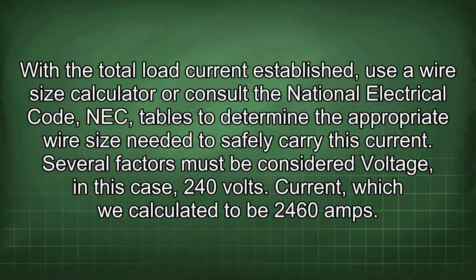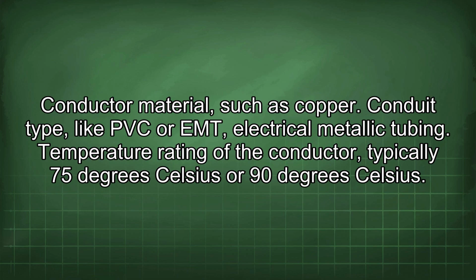Current, which we calculated to be 2460 amps. Conductor material such as copper. Conduit type like PVC or EMT, electrical metallic tubing. Temperature rating of the conductor, typically 75 degrees Celsius or 90 degrees Celsius.